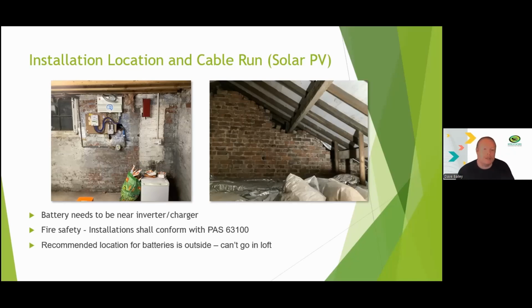This change has been quite tricky for solar installers because there isn't always a great location. It can't go in a loft, it can't go under the stairs because that could cut off an escape route if there's a fire. Wherever it is, it needs to be fireboarded to be safe. While this document is only a recommendation at the moment, it's the current industry advice and installers should conform to it. If there's backlash, it might not make it into the next amendment of the 18th edition, but until it does, everyone needs to abide by this document and install it safely in one of the approved locations.